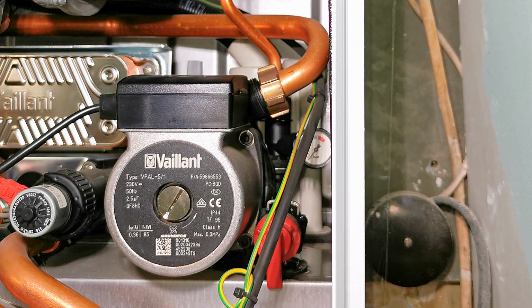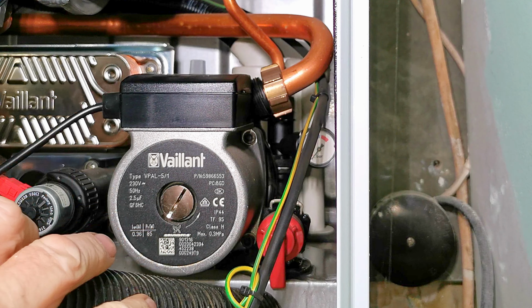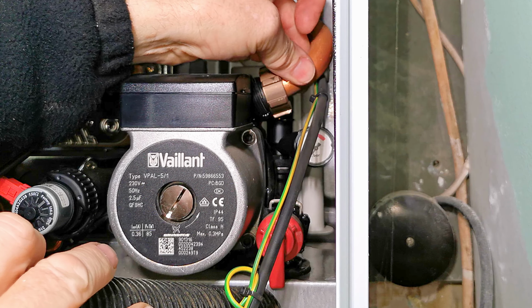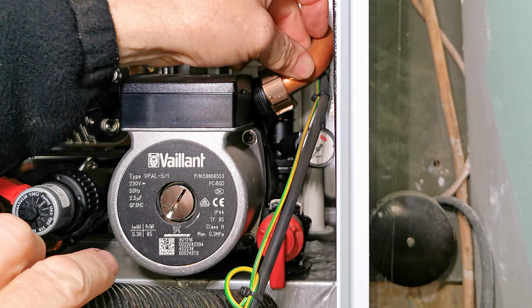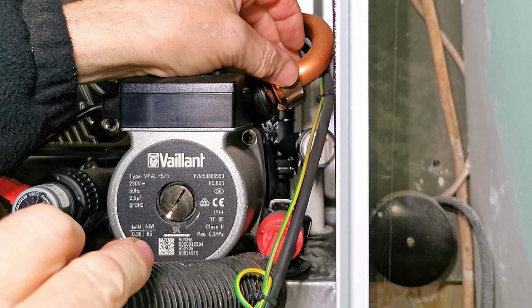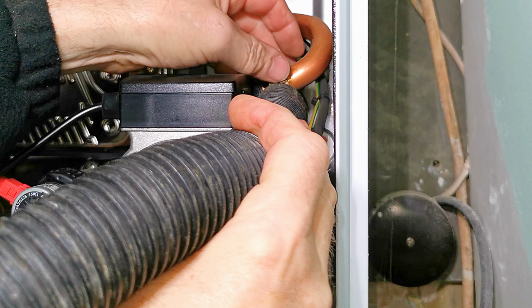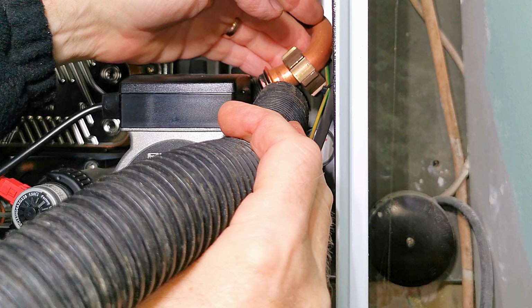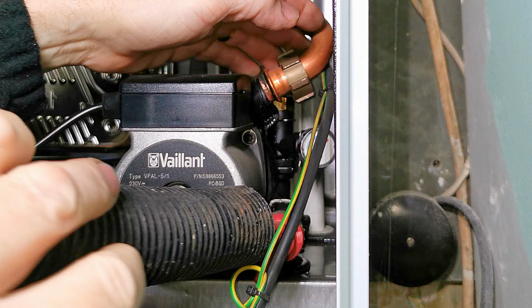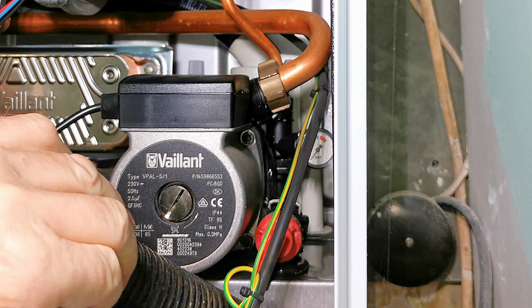Now I've got my water vacuum because as soon as I remove this pipe I'm going to get lots of water come running out. So I gently pull that pipe off and there we go, you can see all that water come gushing out of the boiler. I'm just going to use my vacuum, like I said, just catch all that water. It's just the water which is up inside the heat exchanger and any other pipework within the boiler.